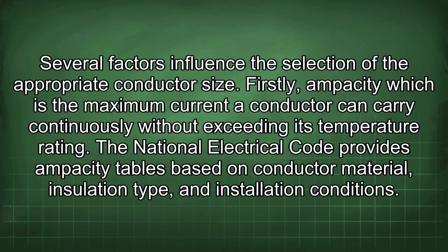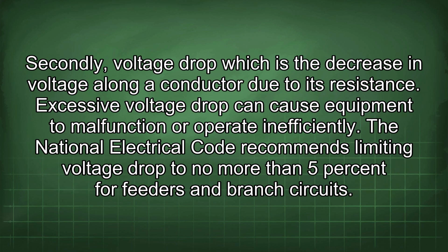Several factors influence the selection of the appropriate conductor size. Firstly, ampacity, which is the maximum current a conductor can carry continuously without exceeding its temperature rating. The National Electrical Code provides ampacity tables based on conductor material, insulation type, and installation conditions. Secondly, voltage drop, which is the decrease in voltage along a conductor due to its resistance. Excessive voltage drop can cause equipment to malfunction or operate inefficiently. The National Electrical Code recommends limiting voltage drop to no more than 5% for feeders and branch circuits.